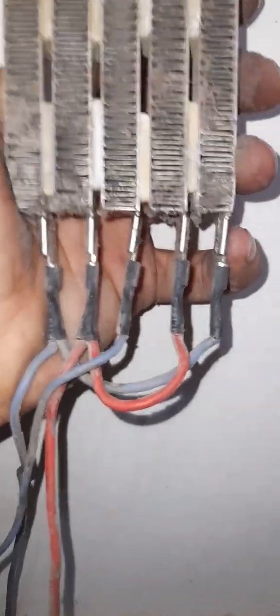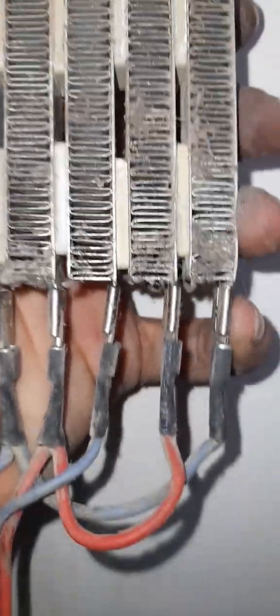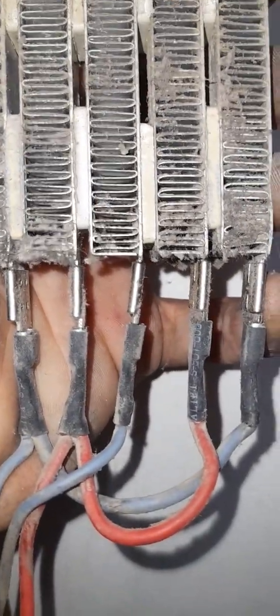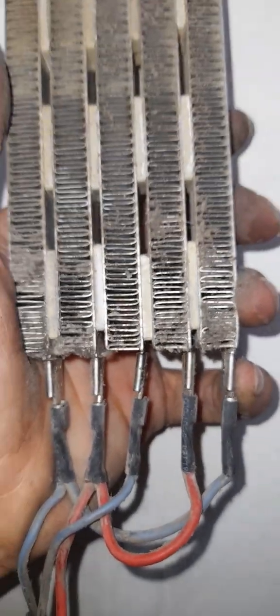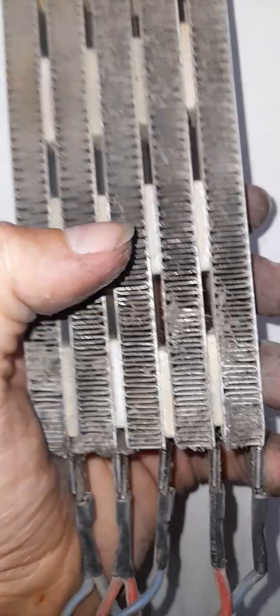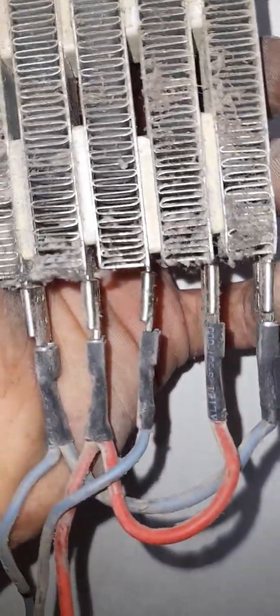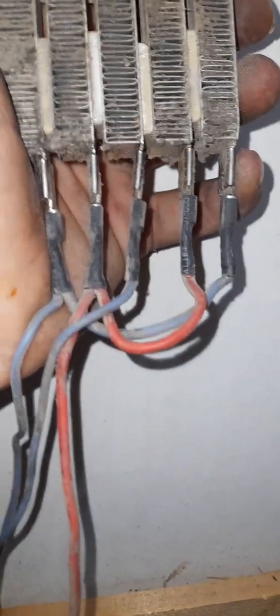You can see here the jumper from this fuse. It goes here into the primary internal entry of the heating element. So if they are connected as the jumper is connected, the neutrals are in parallel.